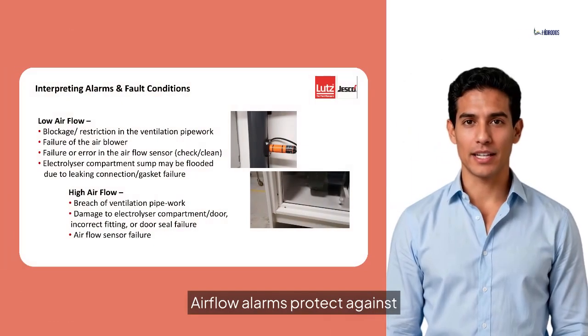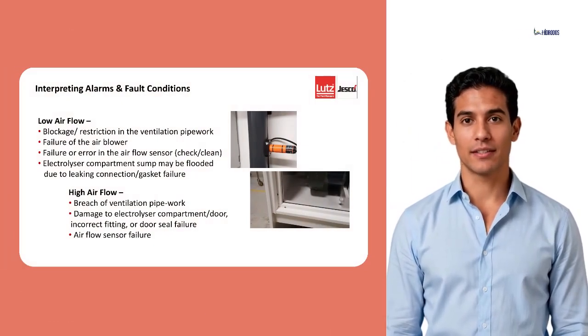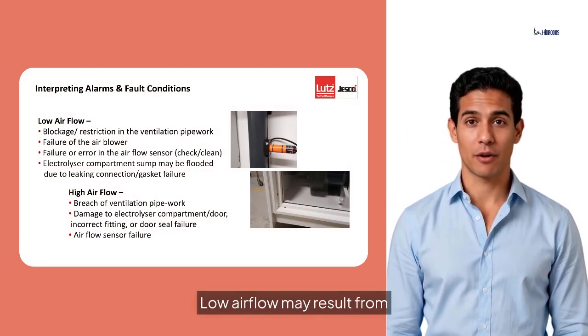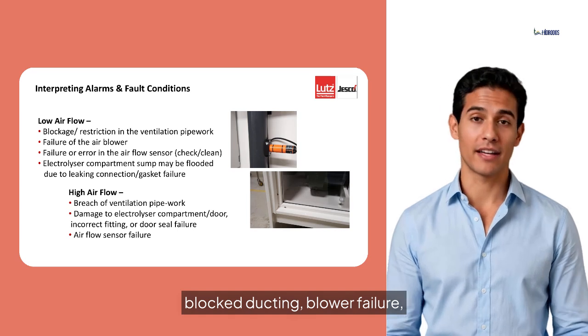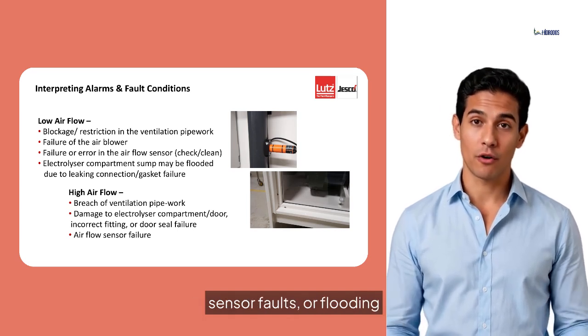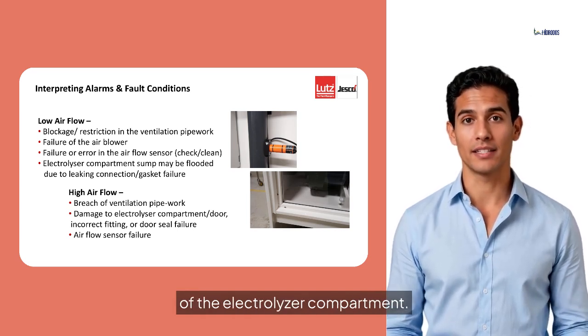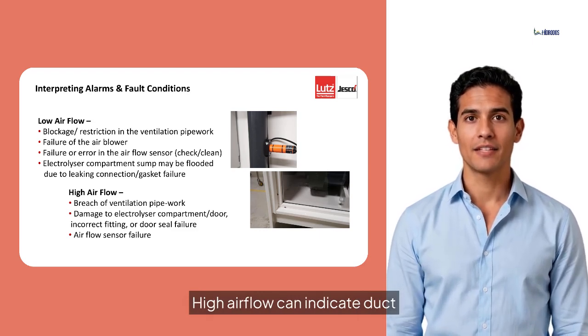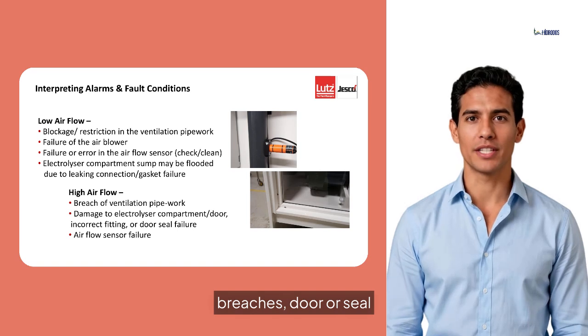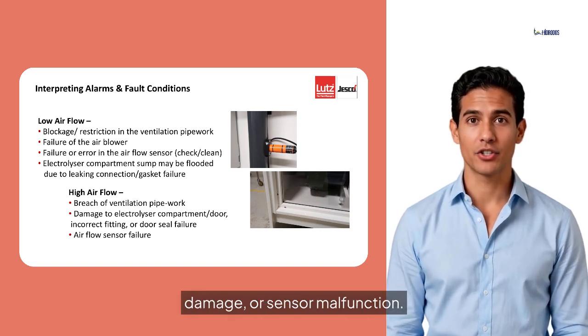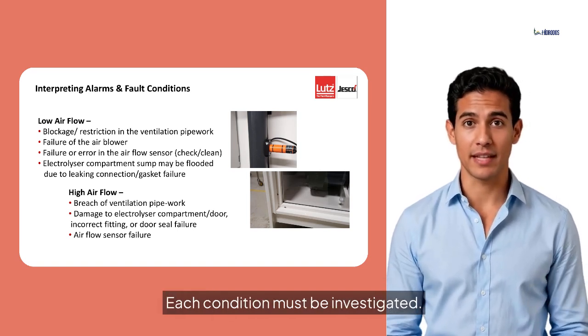Airflow alarms protect against hydrogen accumulation. Low airflow may result from blocked ducting, blower failure, sensor faults, or flooding of the electrolyzer compartment. High airflow can indicate duct breaches, door or seal damage, or sensor malfunction. Each condition must be investigated.